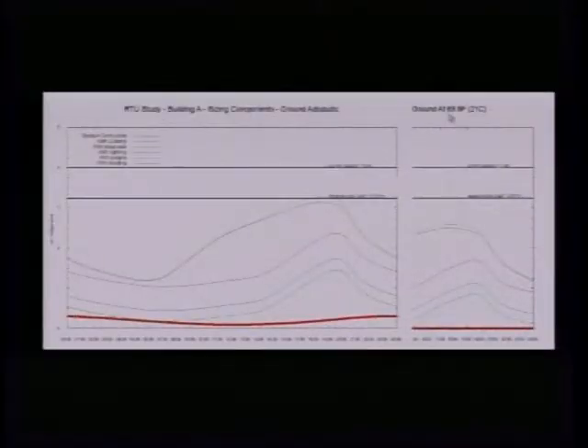But then what if you define a temperature of the ground? This is 21 degrees centigrade, which is conservative, not excessive. Immediately, the peak load decreased, and we are talking about a quarter here, 20%, 25%, and this is significant. It's the safety factor right there, right?